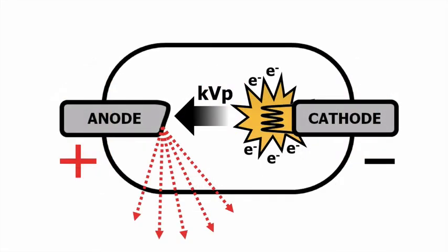In summary, x-rays are not produced by magic or by unicorns. X-ray production requires three basic things: a source of electrons through thermionic emission, a means of accelerating those electrons (that's the KVP), and a means of decelerating the electrons, which is what happens when the electrons slam into the anode. MA is used to control the number of x-rays, and KVP is used to control the energy of those x-rays.